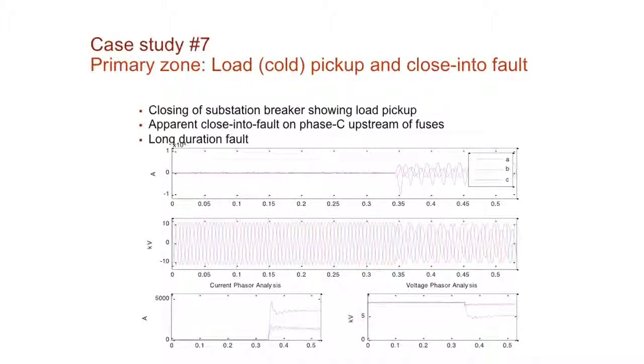Now, what happened here also we noticed was, if you look at this, not only was it picking up some load, but what would you say also happened here? If you look at the RMS magnitude on phase C, what would you say it was also? Because there was a phase A fault. When we caught this, there may have been a phase A fault, and the substation breaker opened and closed. Why would you say it's a substation breaker? We're at the head of the feeder. How would you conclude it's a substation breaker versus a device downstream of the substation? What clue in the first waveform would tell you?